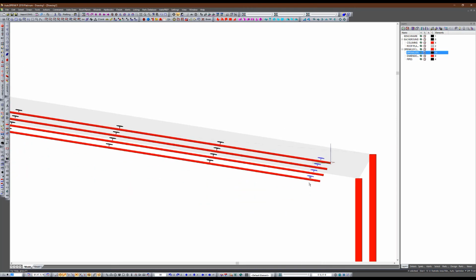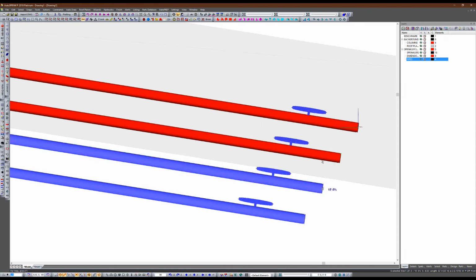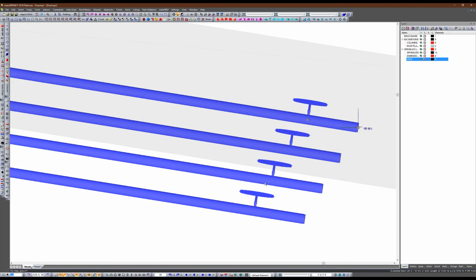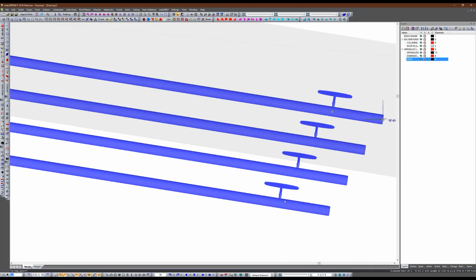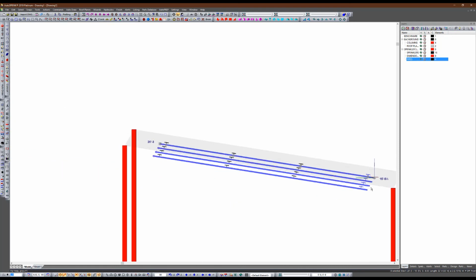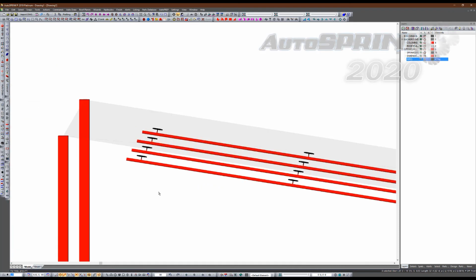So how do I add an outlet there? Well, the easy answer is elevate elements to pipe, select the pipes, run a cleanup intersection. The heads are repositioned, and now the program does kind of the work for us. It adds the outlet and it re-elevates these sprinklers to fit into these outlets. Let me do the same thing. Well, I already did it on that end, or it did it for me, I should say.